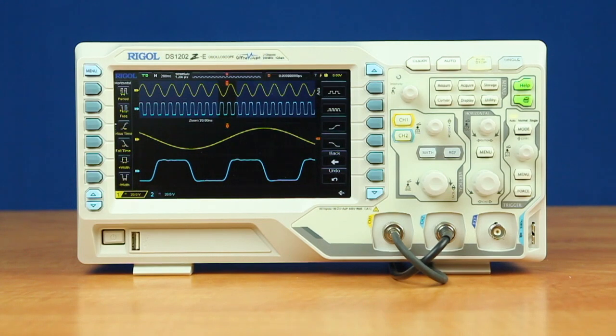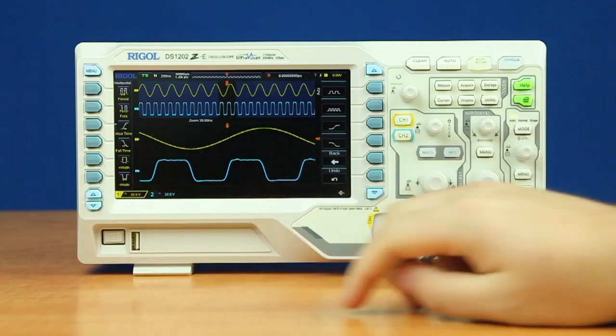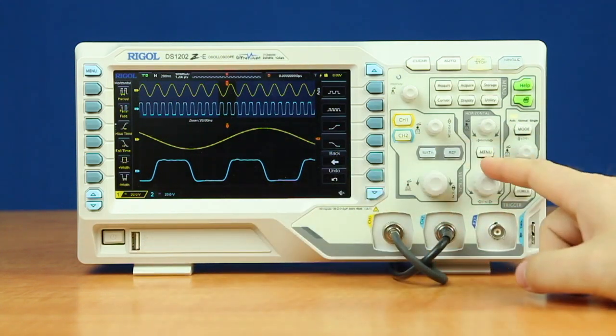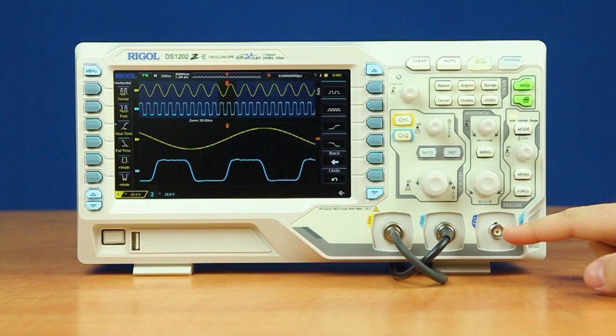On the front panel of the instrument, we have a seven-inch color display. Below that, we have a mechanical power button and USB port, and we have two analog inputs which can be controlled with our vertical and horizontal scaling and position knobs. Then we have an external reference trigger, which can be used with both channels or one channel independently to allow the instrument to trigger on that.